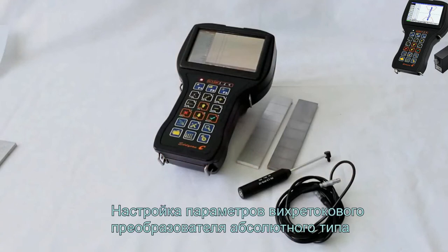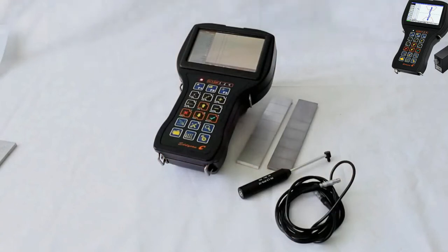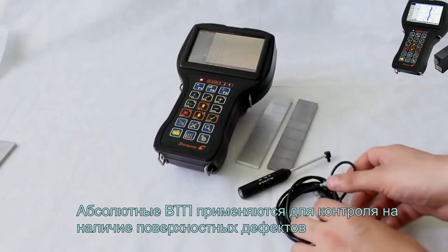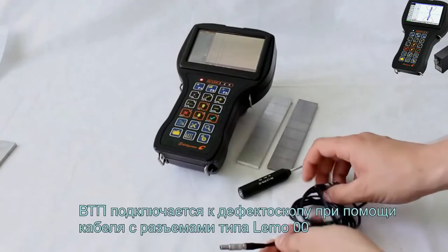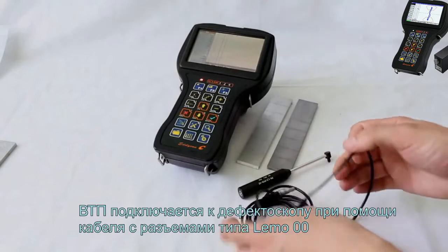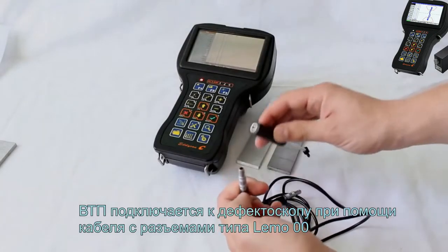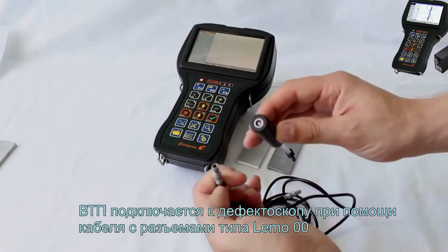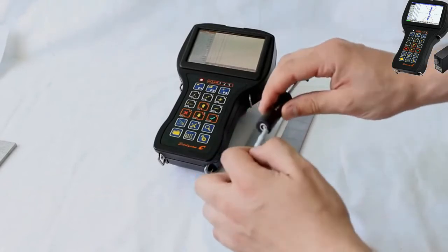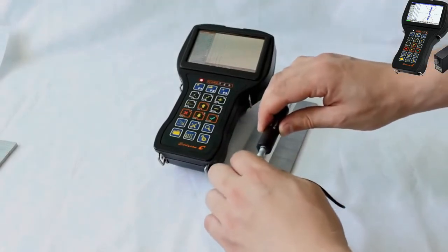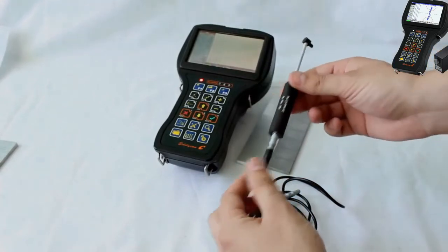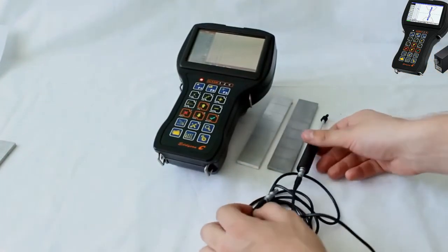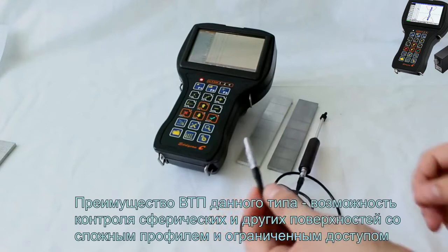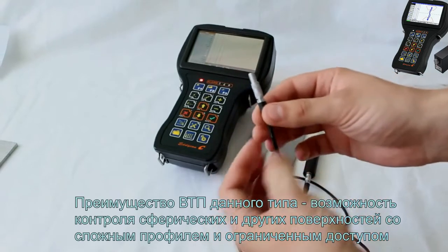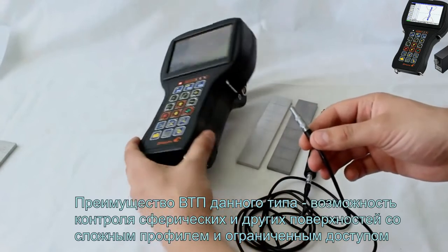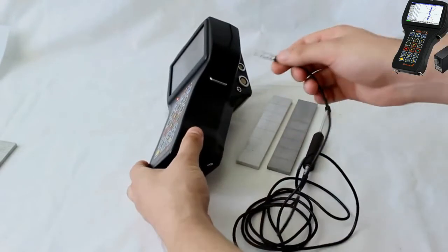Setting up the parameters of Eddycon absolute type probe. Absolute probes are used for detecting the subsurface defects during the testing. Use the Lemo 00 cable to connect the EC probe to the flaw detector. The advantage of this probe is the capability to carry out the testing of spherical and other surfaces with a complex profile and limited access.